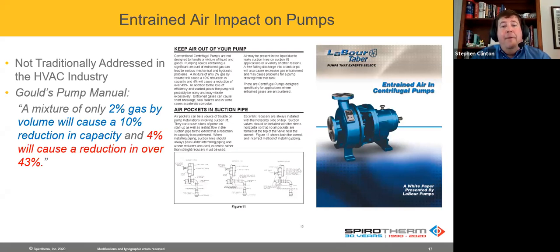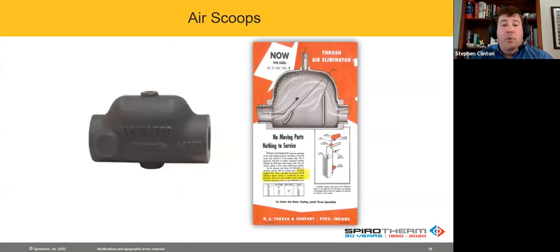Something to consider. Now, in our industry, we've tried to take care of air in different ways over the years. The thing we need to keep in mind is for many, many decades before VFDs really came in vogue 20 to 30 years ago, every system had to operate constant flow because you had three-way valves. You had to flow all the water all the time. You didn't have the benefit of being able to reduce and vary flow. So there were certain pieces of equipment. Two of the most prevalent ones were air scoops. Hey, we allow some of the air bubbles to be removed.